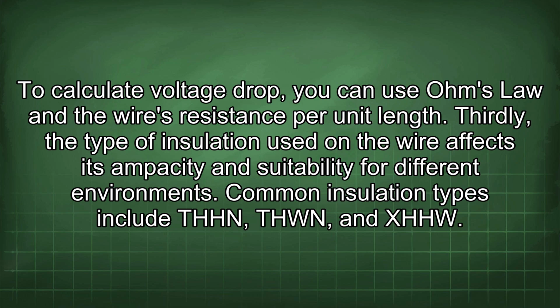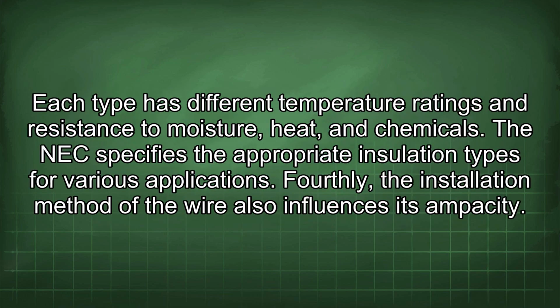Thirdly, the type of insulation used on the wire affects its ampacity and suitability for different environments. Common insulation types include THHN, THWN, and XHHW. Each type has different temperature ratings and resistance to moisture, heat, and chemicals. The NEC specifies the appropriate insulation types for various applications.